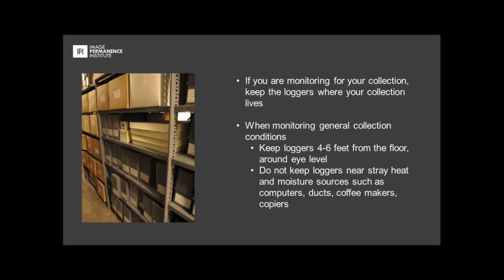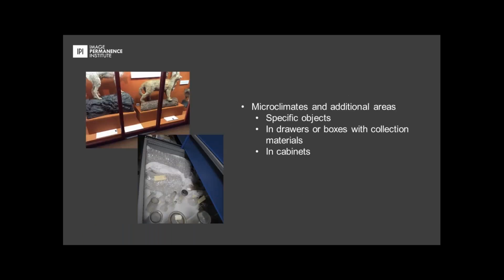Also, do not keep your loggers near stray sources of heat or moisture. We get calls from people saying their data loggers aren't functioning properly, that their RH is too high. When we dig into the issue, we often find the logger was placed behind a computer monitor or over a coffee maker. The errant heat and moisture they emit throws the logger off and gives false readings. So remember that stray heat sources, moisture, ductwork, and similar things can throw loggers off from what you're actually seeing.